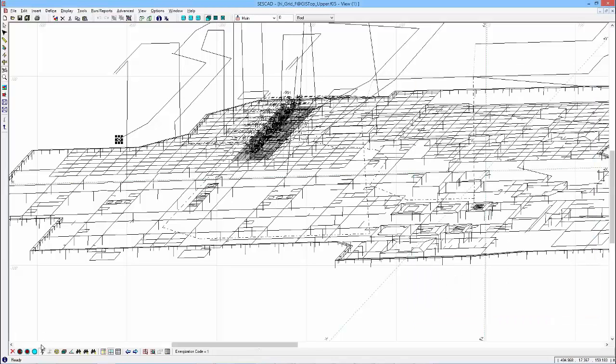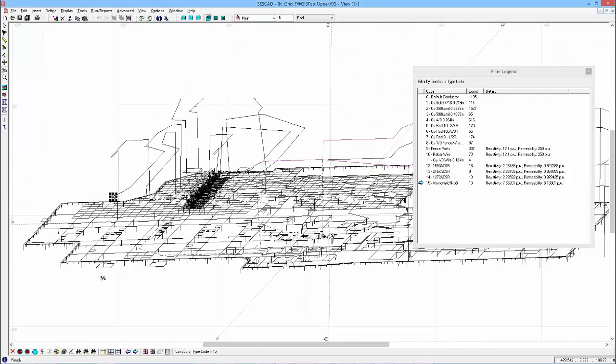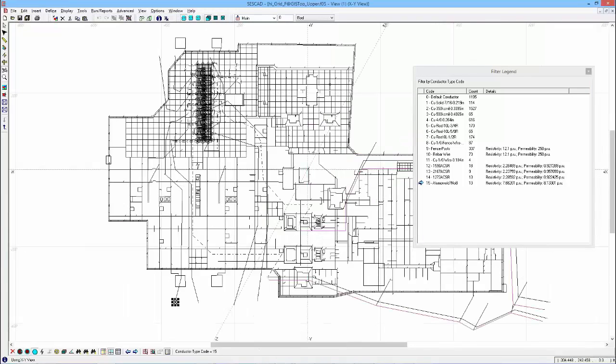The conductor types list is also richer. We include all the conductor types related to the above ground structures, namely the ACSR and AlumoWeld conductors. The fault in this case will be modeled as a simple connection between the faulted phase in question and the grounding system, or the GIS enclosure, and in HIFREQ, anything you want, really. This model is the most accurate and complete depiction of the case possible. So let's look at how it impacts the results.